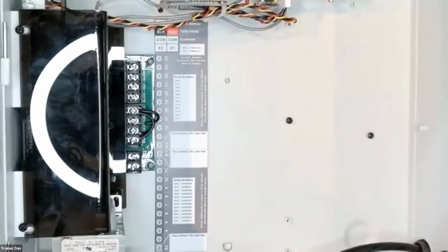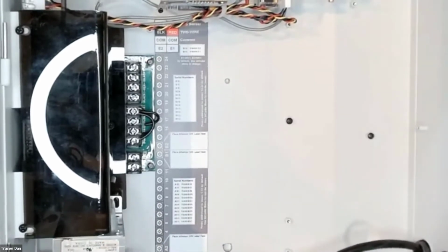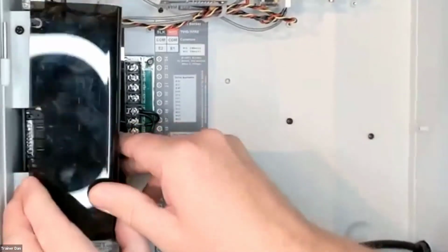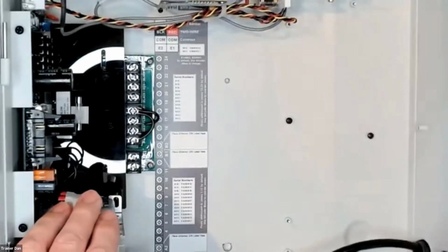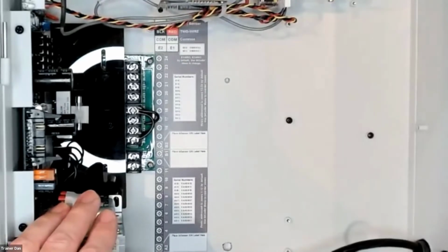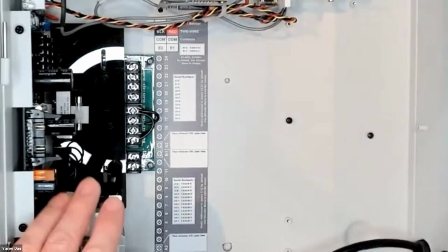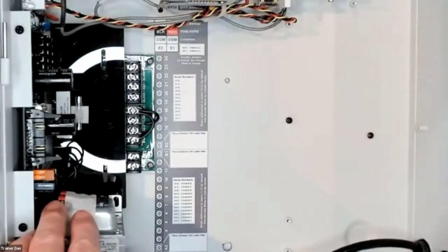So one of the things that we want to check then is, is there power? And to Chris's point, my transformer, let's pull off my cover here so we can see what's going on. My transformer is right down here. Is there power coming into the transformer? That's an excellent question. Is it unplugged? Is the circuit breaker tripped? Is there a problem with the transformer?